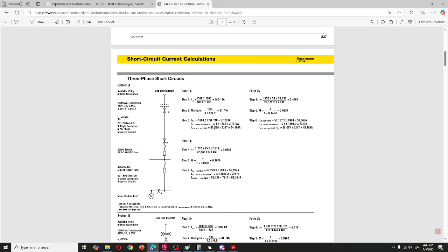For ISC, then for the motor contribution, that's 4 times 1804, which is 7217 amperes. Then total short circuit for RMS is 57,279 plus 7,217 which equals 64,496 amperes.